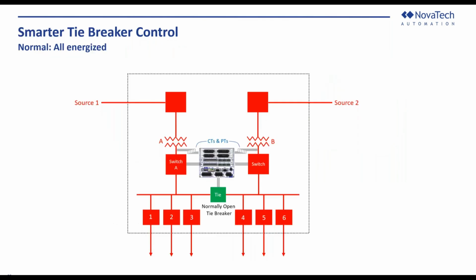The next application we'll talk about is smarter tie breaker control. The simple parallel substation there with a normally open tie breaker, source 1, source 2. For the purpose of this discussion, we will assume that there are potentially some scenarios where source 1 and source 2 should not be tied to each other. We'll assume that sometimes they're in sync, sometimes they're not in sync. We'll also assume that under certain loading conditions, different times of the day, different times of the year, it might be impossible for source 2 to pick up the full load of the 6 feeders, or for transformer B to pick up the full load of those 6 feeders.